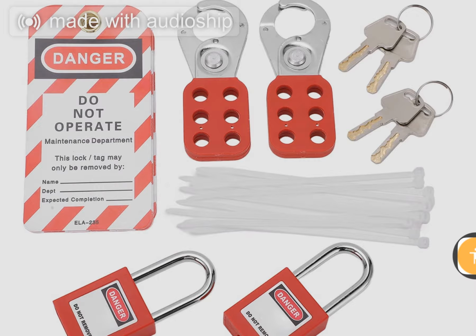Okay, after the FR clothing, we're talking about hands. A critical system. You need insulated gloves rated for the maximum voltage you could encounter. But here's the part people miss. You always have to wear leather cover gloves over them. Why is that? The rubber is the insulator, but it's fragile. A tiny nick or puncture makes it useless. The leather protects the rubber. And finally, your head and your face. For any task with an arc flash risk, you need an arc-rated face shield or a full hood. An arc blast is instantaneous, a plasma explosion. That hood is the only thing between that blast and your face and lungs.